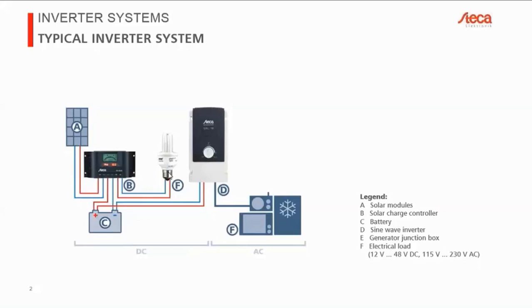And you'll see later this basically helps reduce the total consumption, because your inverter always has a certain amount of self-consumption. So in the typical design, we have a DC load as well, so this is optional, of course. Then we have the inverter, which is D. You'll notice here the inverter is directly connected to the battery. It is not connected to the DC output of the charge controller.